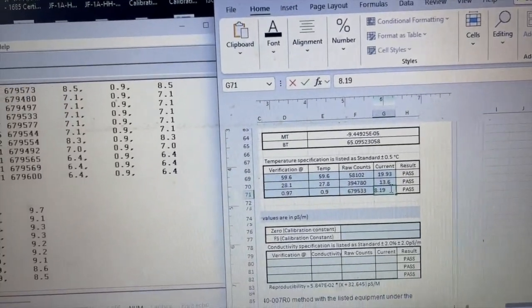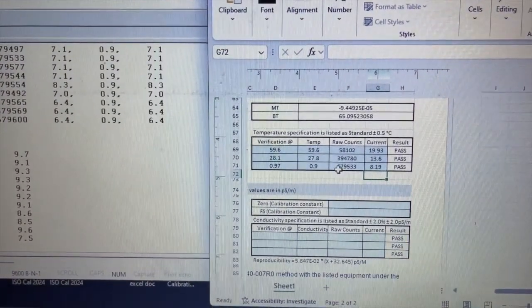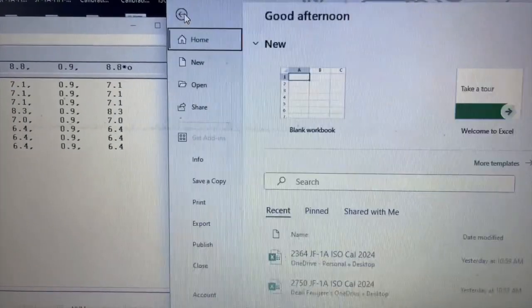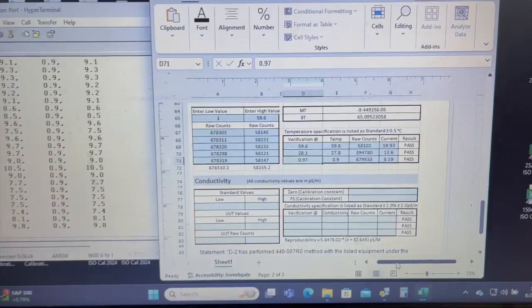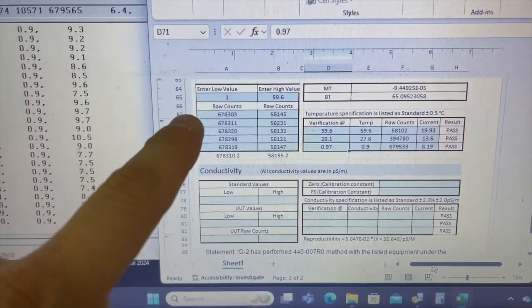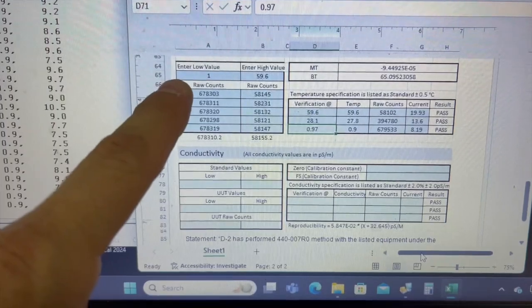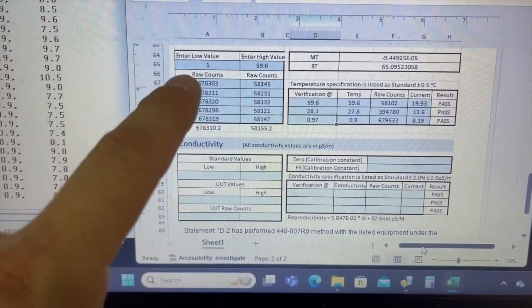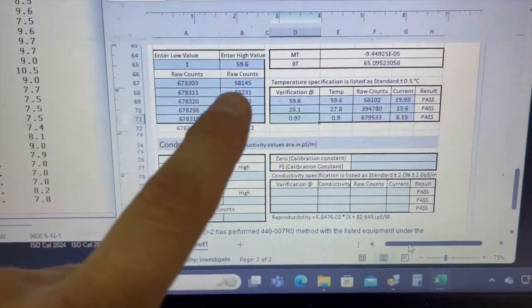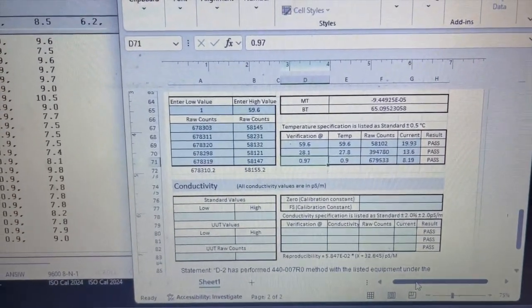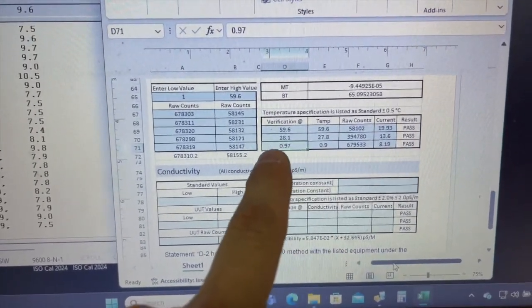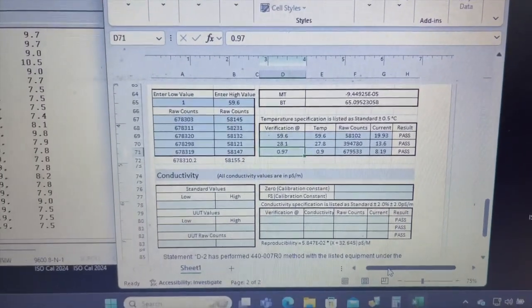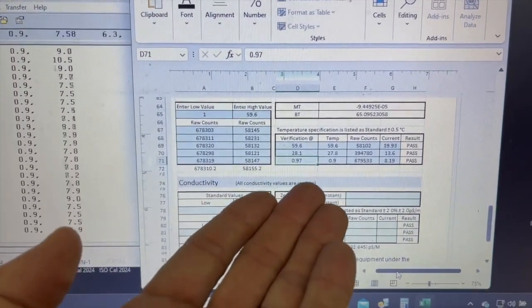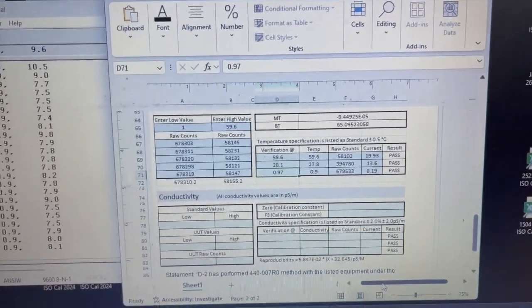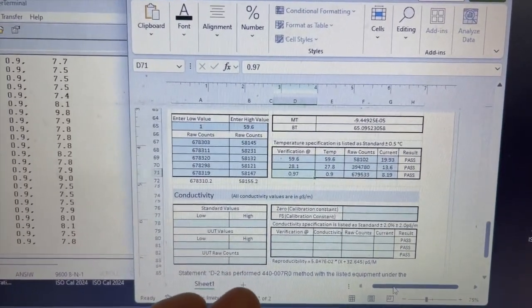So it's 8.19 volts, or sorry, mA, milliamps, and that is a wrap, so I generally save it here at this point, and then we move on to conductivity. The main part here is we used a NIST traceable temperature thermometer to get our reference values, and then we were able to use the sensor counts to get a low point and a high point and do linear calibration across the 2 points, which when checked against various measurements comes out to be exactly what we are looking for. So therefore, NIST traceable temperature within 0.5 degrees Celsius, and that's all been verified. Now we can move on to conductivity.